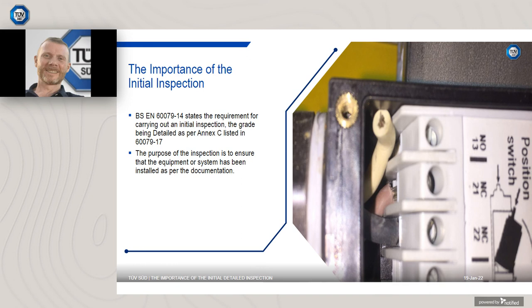The importance of the initial inspection. BS EN 60079-14 states the requirement for carrying out an initial inspection, the grade being detailed as per Annex C listed in 60079-17. Other inspection types are periodic, continuous, and sample. The grades are close and visual. The purpose of the initial inspection is to ensure that the equipment or system has been installed as per the documentation.